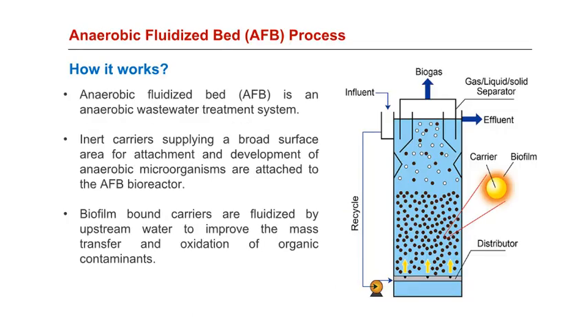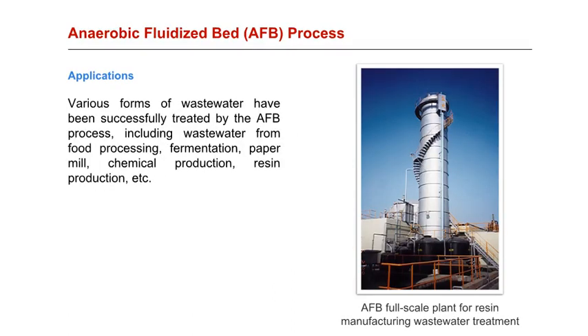Anaerobic fluidized bed, or AFB, is an anaerobic wastewater treatment system. Inert carriers supplying a broad surface area for attachment and development of anaerobic microorganisms are attached to the AFB bioreactor. Biofilm-bound carriers are fluidized by upstream water to improve the mass transfer and oxidation of organic contaminants. Various forms of wastewater have been successfully treated by the AFB process, including wastewater from food processing, fermentation, paper mill, chemical production, resin production, and others.